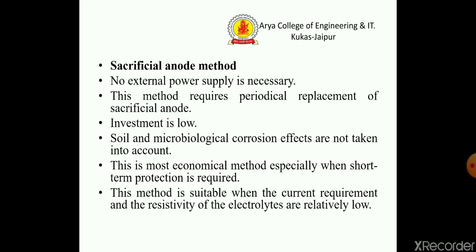The difference between sacrificial anodic method and impressed current method: in the sacrificial anodic method, no external power supply is required; this method requires periodical replacement of the sacrificial anode; investment is low; soil and microbiological corrosion effects are not taken into account; it is the most economical method when short-term protection is required; and it is suitable when the current requirement and resistivity of the electrolyte are low.